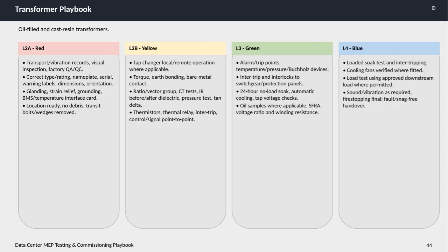On this slide, we are focusing on the transformer playbook, specifically for oil-filled and cast resin transformers, which is a critical part of the data center MEP testing and commissioning playbook. The process is divided into 4 key levels, each associated with a color code that helps organize and prioritize the tasks. Starting with level 2A, marked in red, this stage is all about ensuring the transformers arrive in perfect condition.